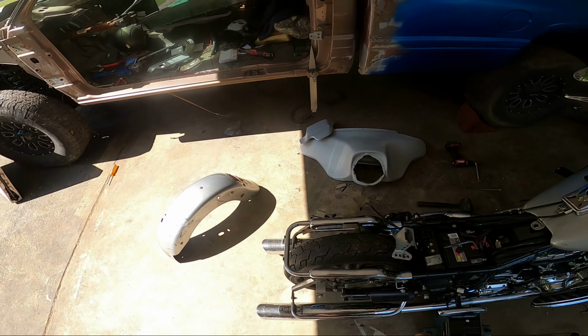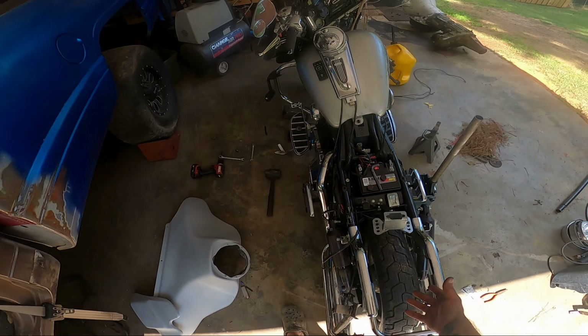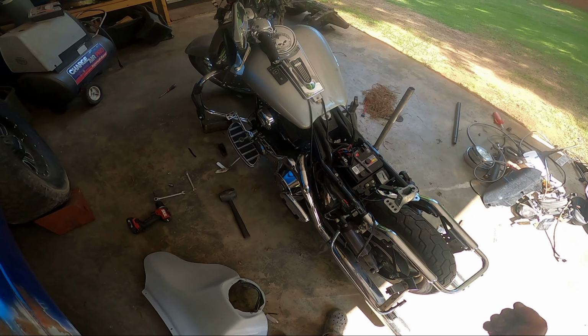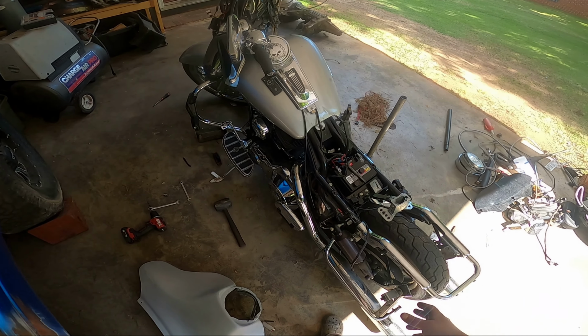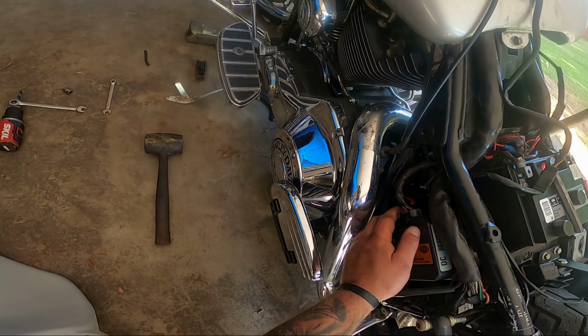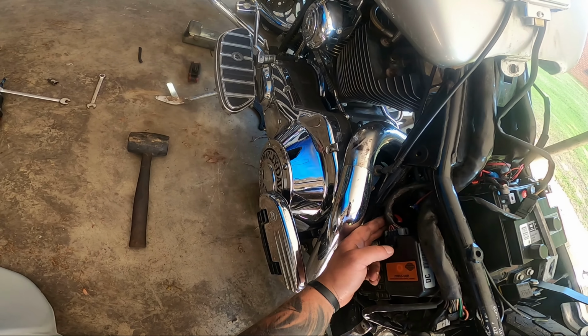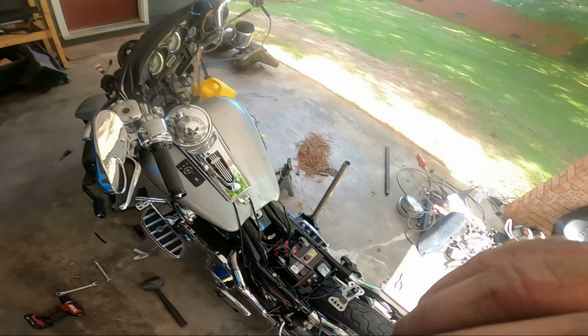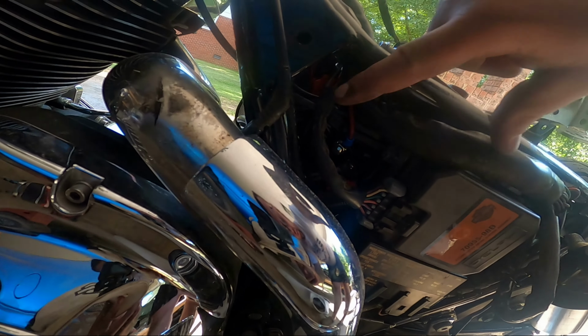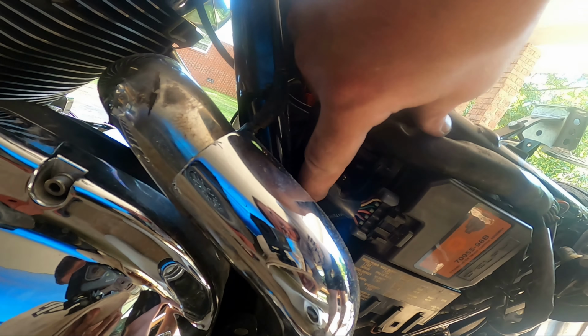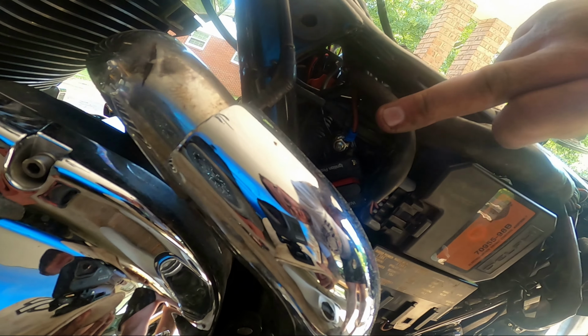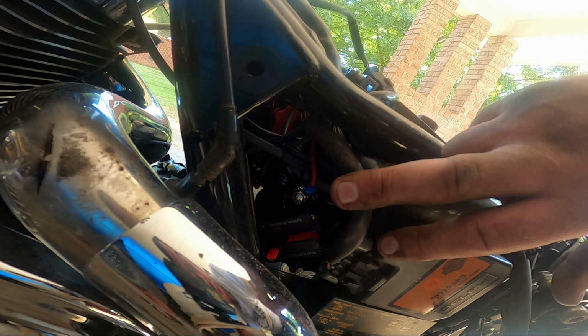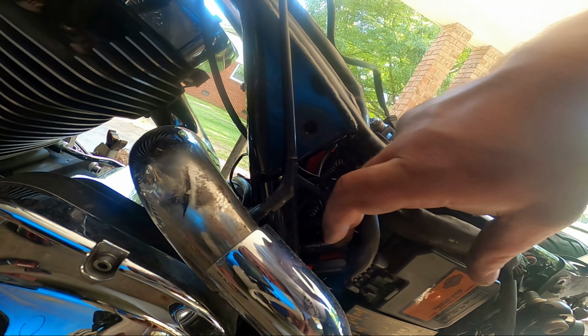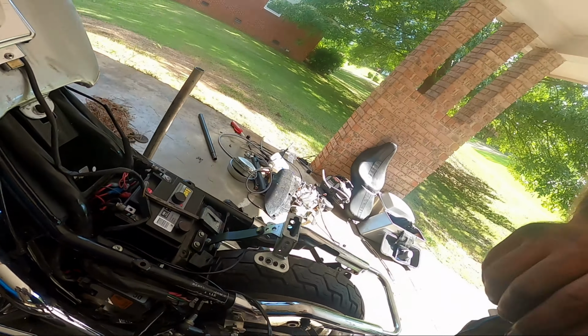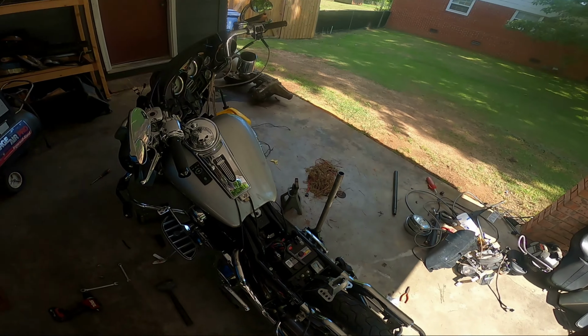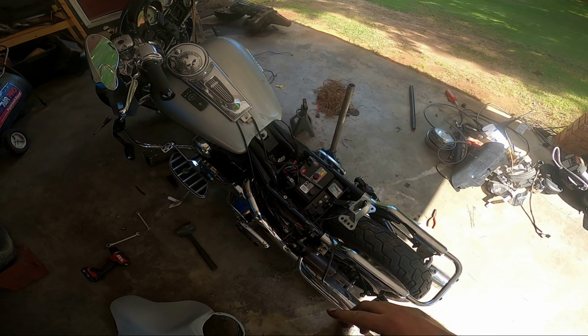So I talked to another guy. He said these things come with a stock 30 amp circuit breaker, and that's entirely too small. If you could find a marine grade 60 amp circuit breaker - you can't really see it, but down in here you can see the lugs for it. If it ever trips, instead of resetting automatically, I just push this little flag back down and it resets. That's not the permanent spot we're gonna mount it, that's just where I have it right now.